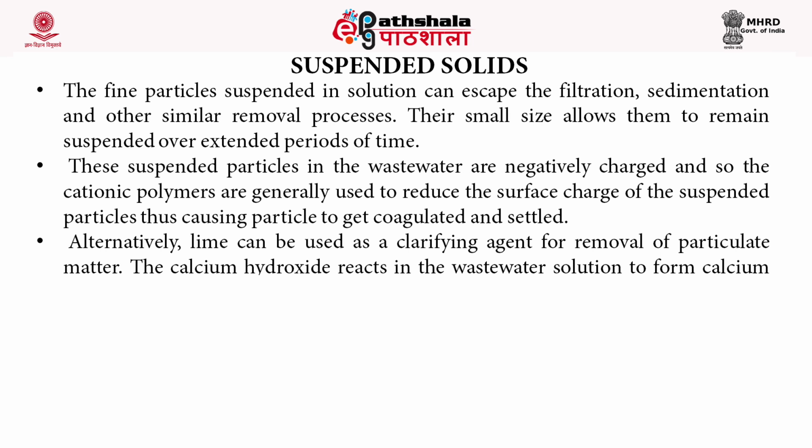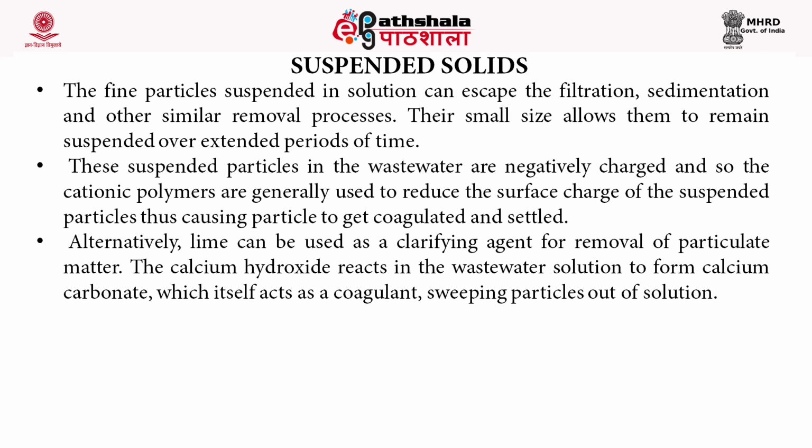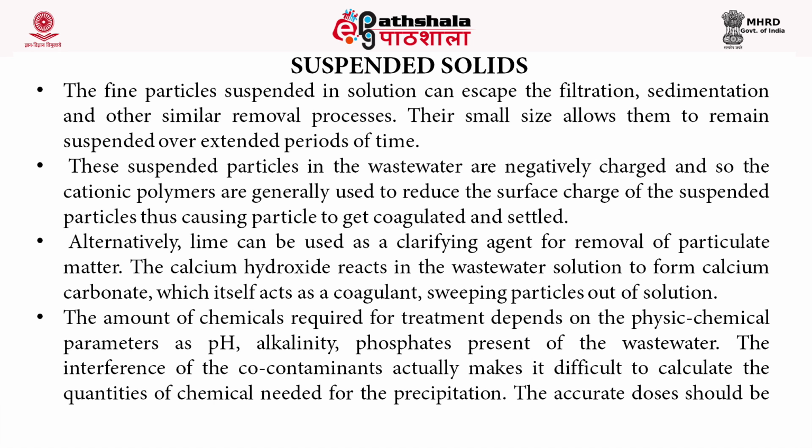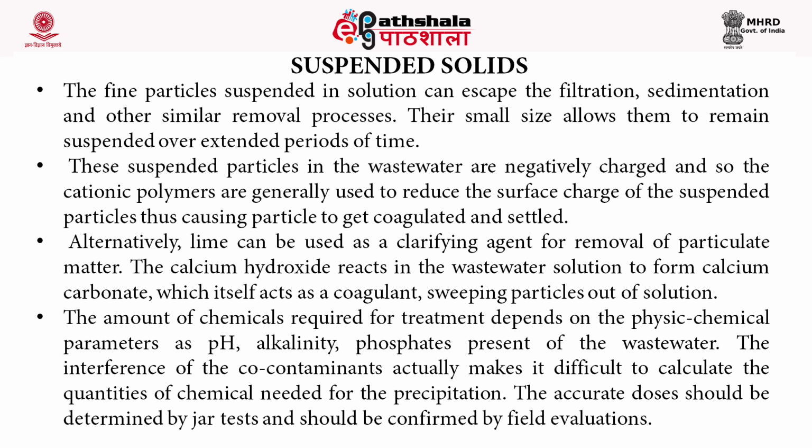Alternatively, lime can also be used as a clarifying agent for the removal of this particulate matter. The calcium hydroxide reacts in wastewater solution to form calcium carbonate, which itself acts as a coagulant, sweeping the particles out of the solution. The amount of chemicals required for the treatment depends upon the physicochemical parameters like pH, alkalinity, and phosphates present in the water to be treated. The interference of co-contaminants makes it difficult to calculate the quantities of chemicals needed for the precipitation process. So, the accurate dose should be determined by jar test and should be confirmed by field evaluations.